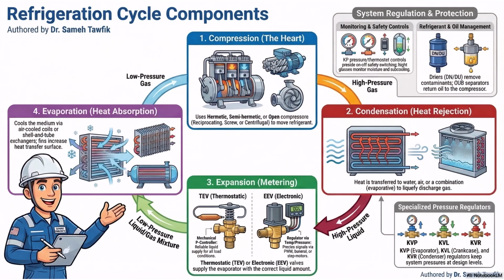Okay. But, as the maritime syllabus points out, modern ships are increasingly moving toward the EEV. The electronic expansion valve. Right. Instead of relying on boiling fluid and springs, the EEV is controlled by a digital regulator receiving constant temperature and pressure signals. Much more modern. Yeah, it uses precise electronic mechanisms, like pulse width modulation or a tiny step motor, to adjust the valve opening. It allows for a level of micro-precision that a mechanical spring simply cannot match. So our bouncer drops the pressure, letting this perfectly measured amount of low-pressure liquid enter the evaporator. And this is the chiller.